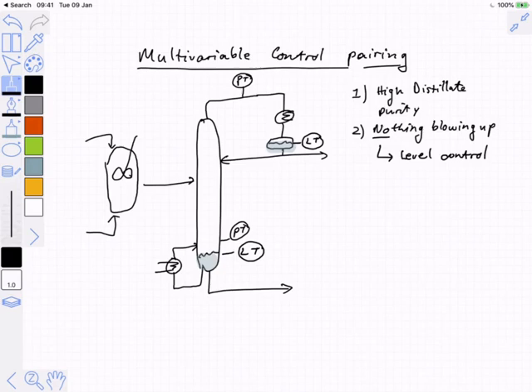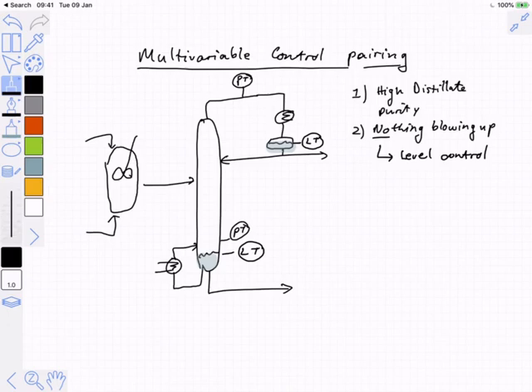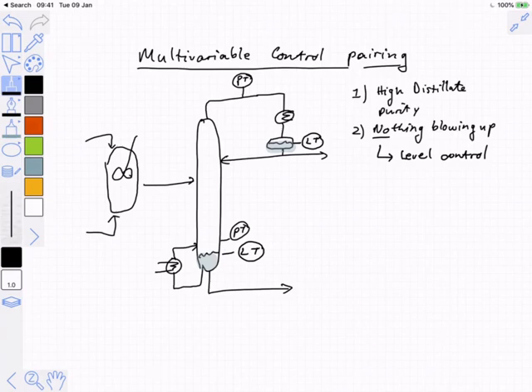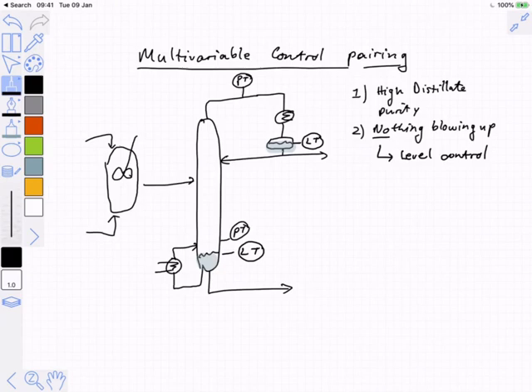What other balances do we have? Level and pressure are the states of the mass balance for liquid and vapor systems. We have energy balances too — blowing things up means violating one of the balances. What could be dangerous if it accumulates? Energy. So we stick an energy meter into our system — that's temperature. We need to make sure somewhere that we're not breaking anything with regard to temperature.